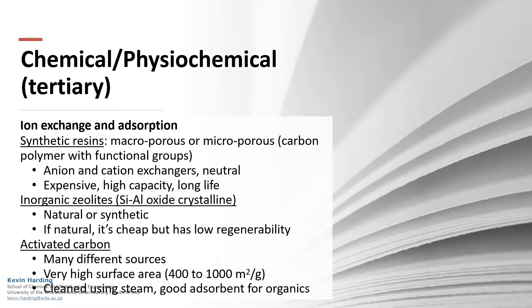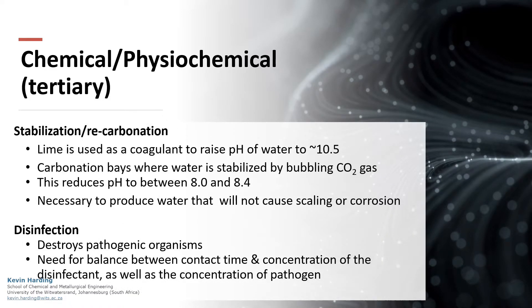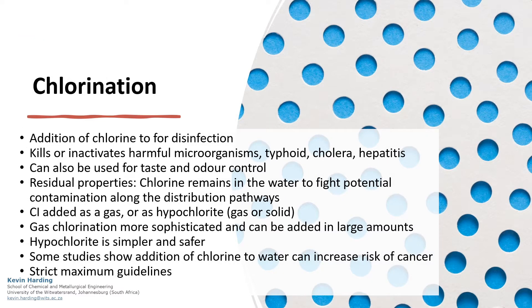The final step in wastewater treatment, the tertiary treatment, utilizes activated carbon, zeolites, or synthetic resins as a means to treat the water. This tertiary treatment step could involve recarbonation by adding lime, or disinfection to destroy any unwanted microorganisms. Disinfection often involves adding chlorine as a solid or a gas to kill harmful microorganisms, but can also be used for taste and odour control.